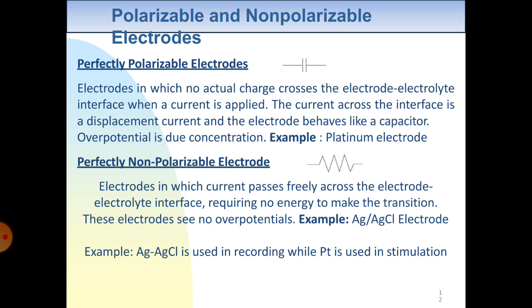Perfectly non-polarizable electrodes are electrodes in which current passes freely across the electrode-electrolyte interface, requiring no energy to make the transition. In the case of perfectly polarized electrodes we need energy, but for perfectly non-polarizable electrodes we do not need energy for transition. An example is the Ag-AgCl electrode. The Ag-AgCl electrode is used in recording, while platinum is used in stimulation.